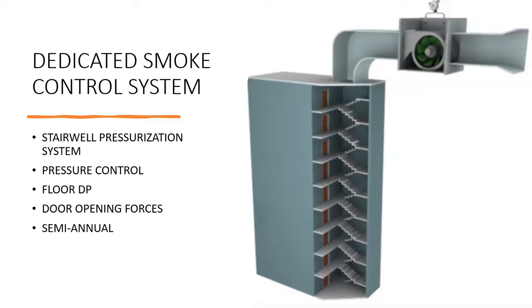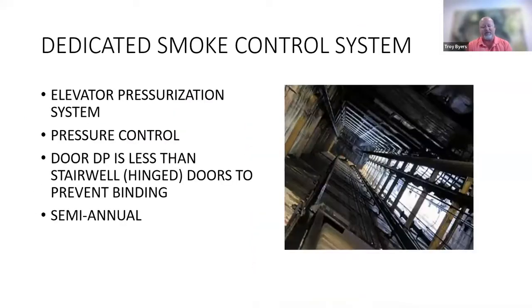Yeah, do note that a lot of this, when I monitor stuff on the TAB side, we typically aim for the low end of that pressure range, the 0.15 for you and 0.1 for me, because of the door closure force on some of those doors when the system isn't on. You want to reduce that swing pressure they have on closure devices, especially to a garage or something that's open and not enclosed. But yes, absolutely. So there are several different angles we need to look at there.